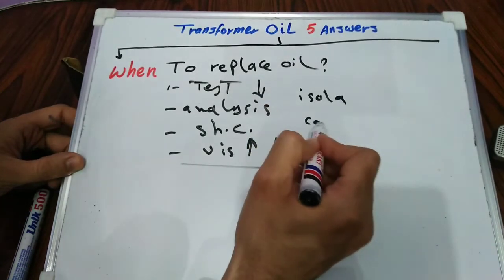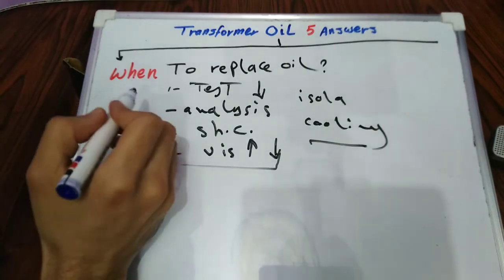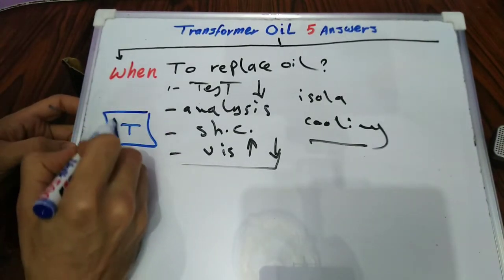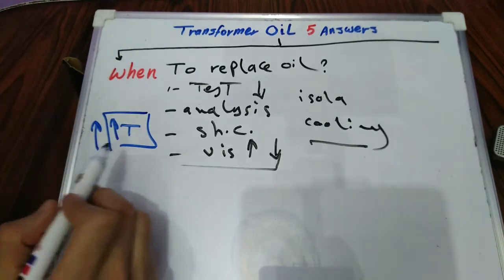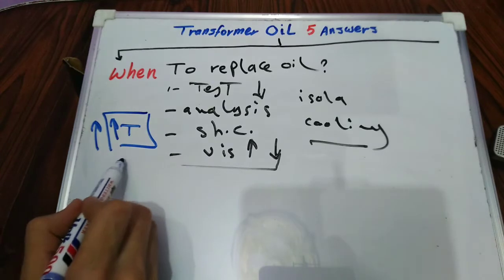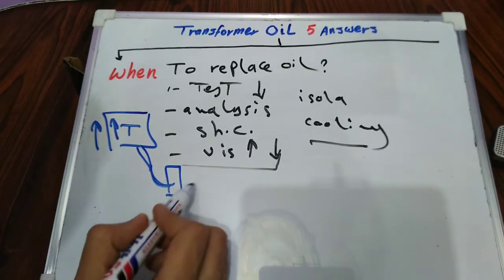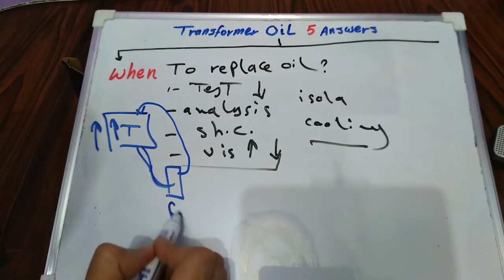It's important to make oil analysis periodically, especially if a temperature rise of the transformer is detected. In my workplace, we noticed that one power transformer temperature rise is abnormal. A good oil analysis showed us that the oil is very wet. We used oil filtration machine to enhance the oil properties. Then we made a dielectric voltage test to make sure the oil is good for the transformer.